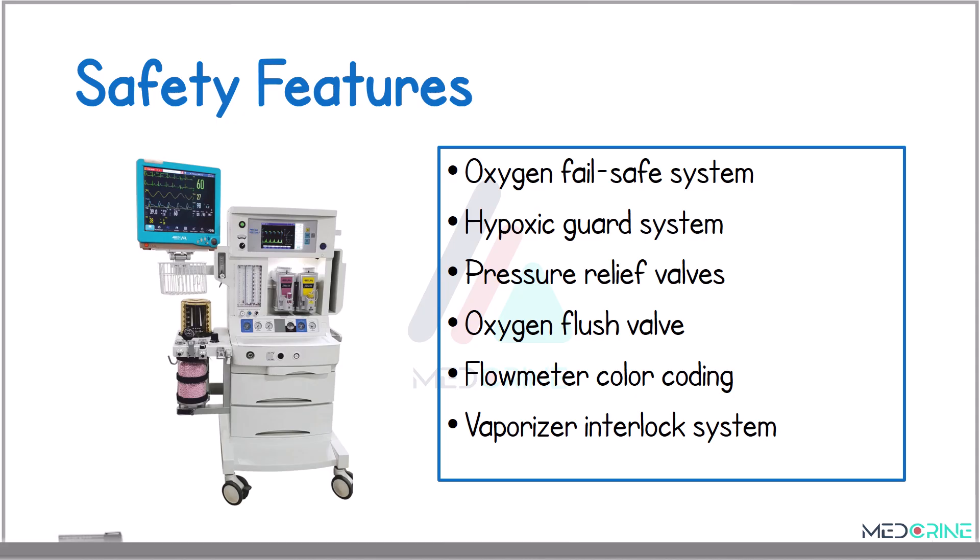Some of the safety features of anesthesia machines include an oxygen fail-safe system, a hypoxic guard, pressure relief valves, an oxygen flush valve, flow meter color coding, and a vaporizer interlock system to prevent multiple agents from running simultaneously.